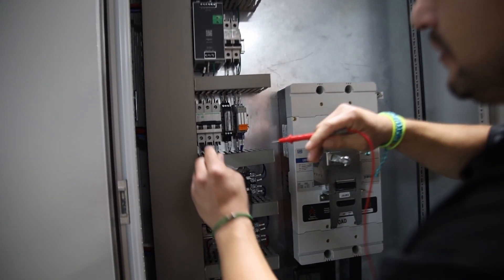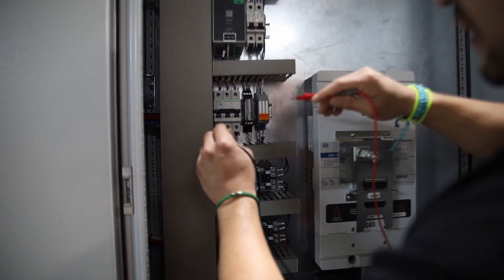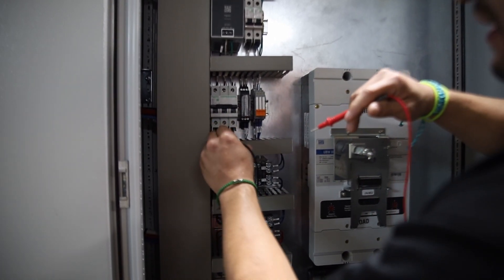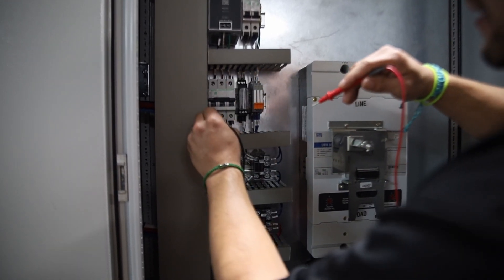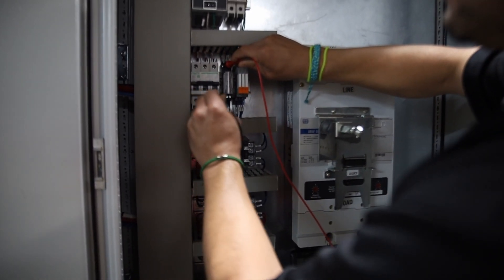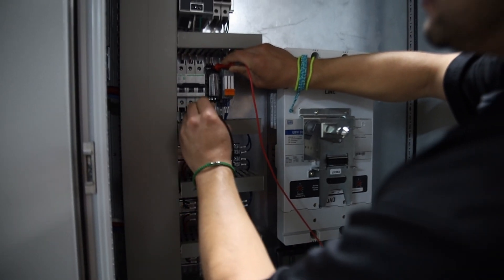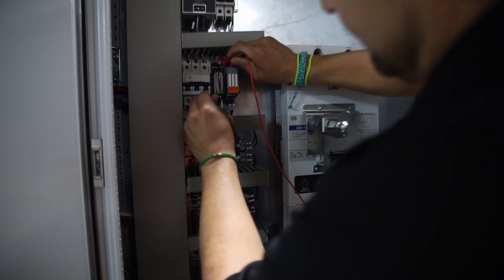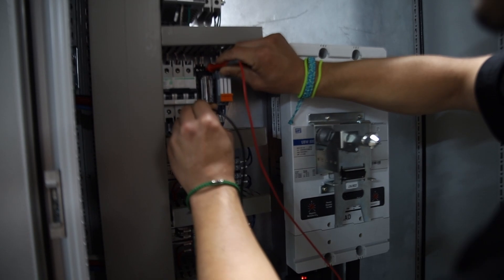The other one too is, for instance, you want to check where this terminal and this wire is going to. We know in the schematic it's landed here and here, but we want to make sure that it is. So we go here to here - see, you check the other ones, you don't hear the beep. You go to the center one, it should be here. Next one, see, we have... there we go. So we know those are going here like they should, and that's how we check point to point.